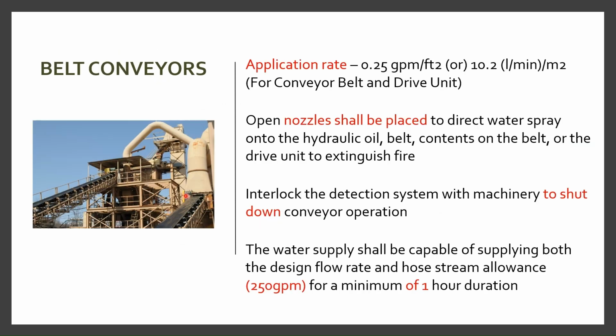So in industrial projects, we have belt conveyors and drive units. So we need to protect all the hydraulic oil as well. We want to make sure that when the fire system operates, we shut down the equipment. We want to stop moving the burning material. In that case, we need to consider the application rate as 0.25 GPM per square feet for conveyor belts and drive units. And also please note, we need to protect the belt, which means we need to protect it from the top as well as from the bottom.